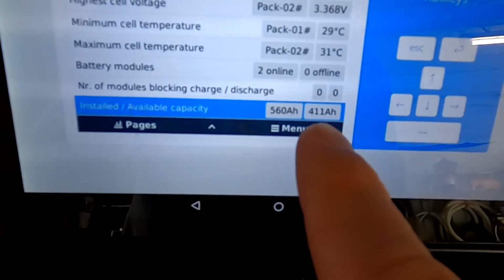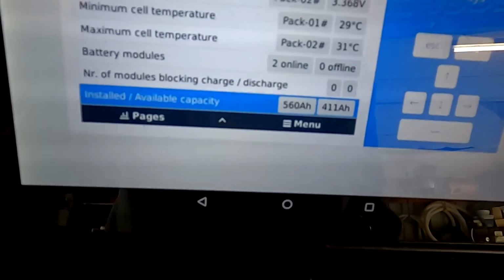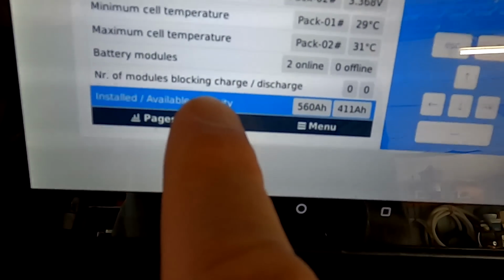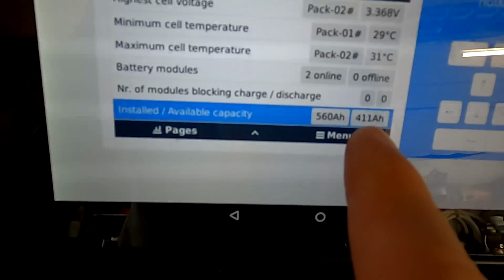Do I have to do a full discharge test with both batteries so it actually learns what's going on? But then again, what is 411 ampere hours available capacity? Is this according to the state of charge at the moment, or is this what we have calibrated the BMSs to? So is this the maximum available capacity of both batteries, which would be wrong as well?